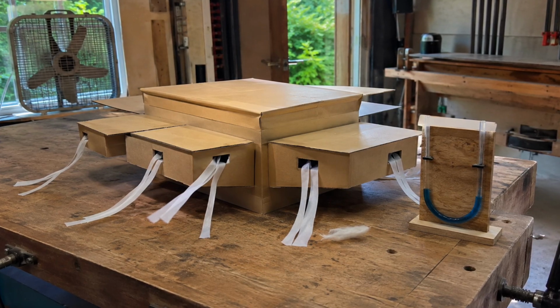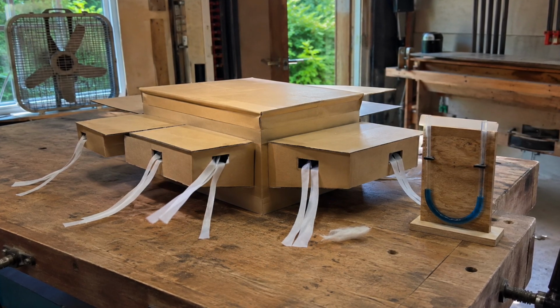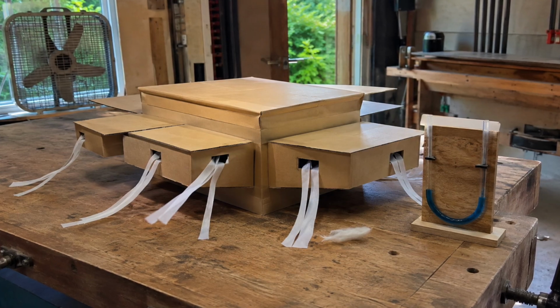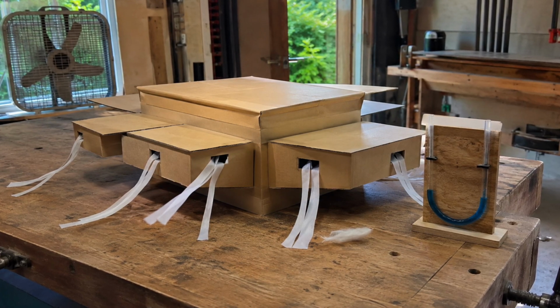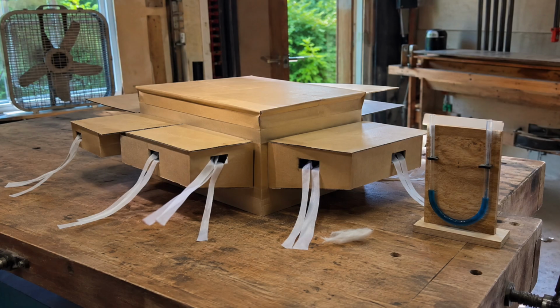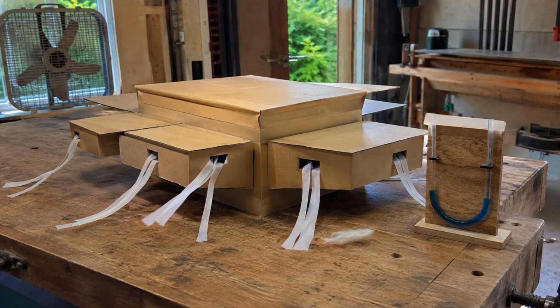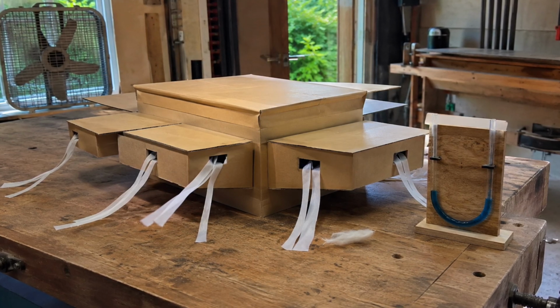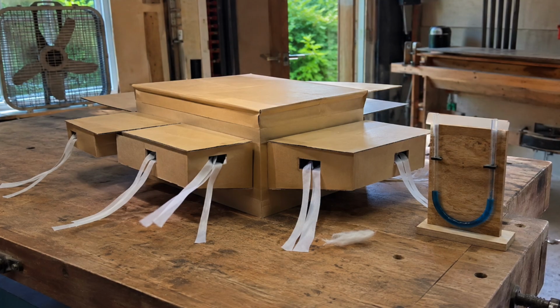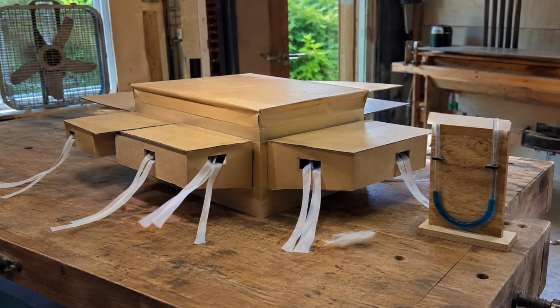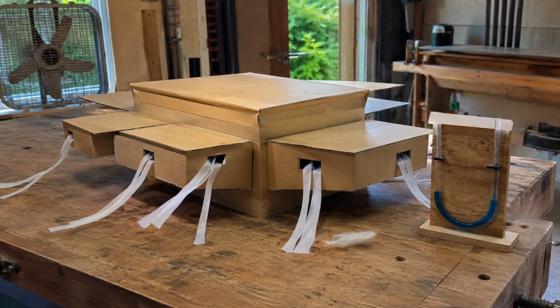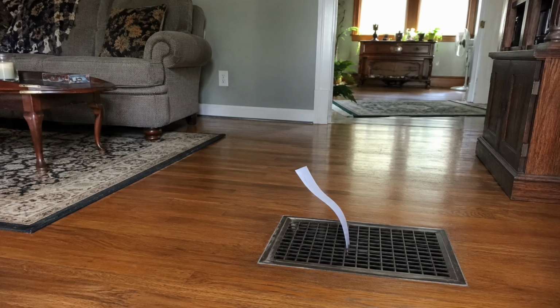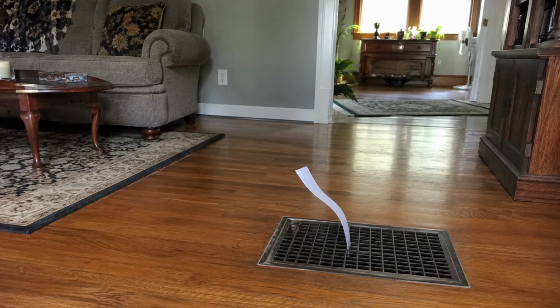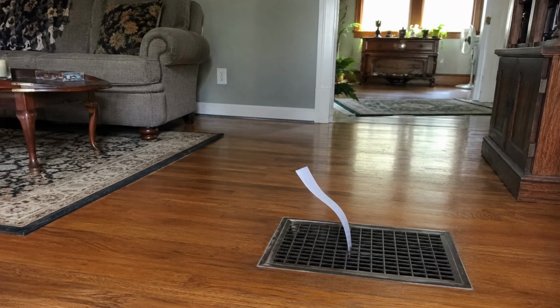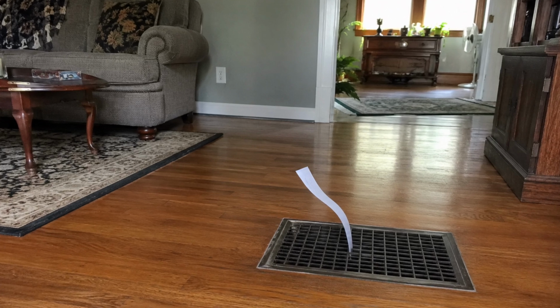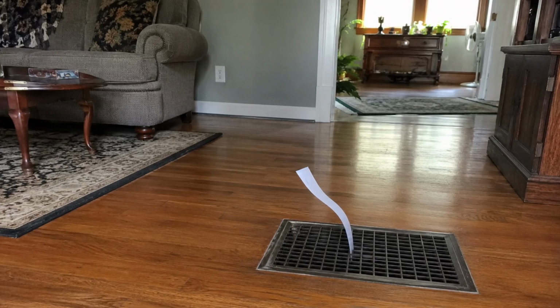Open all 4 holes again. Watch the pressure settle. Watch the streamers share the flow. The box is back to the condition it was built around. That is all the demonstration needs to show. An open path lets the system move air. A blocked path turns some of that movement into pressure and may reduce the total airflow. Now carry the box back to your real house, because in the real machine, the restriction has 2 more places to bite, and one of them can stop your cooling in a July week.